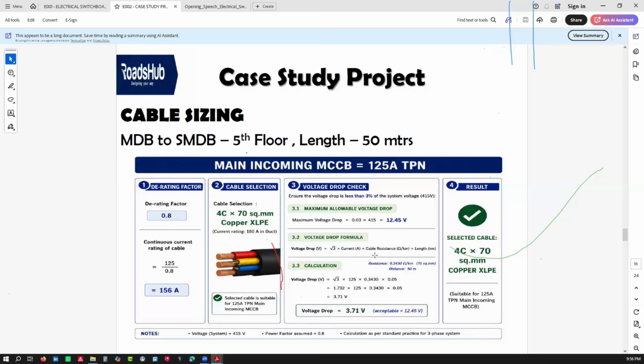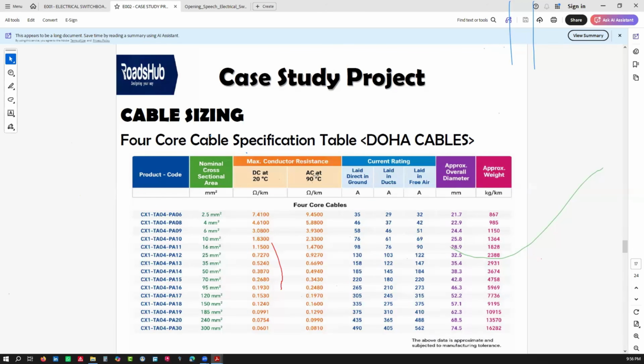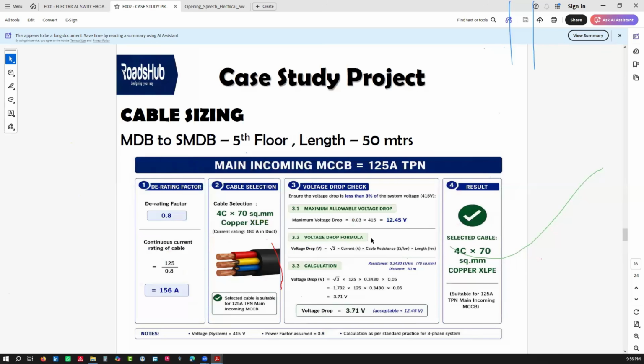So where do you get cable resistance? You have it here at 90 degrees. Always take the highest current and the highest environmental temperature that you have. So you go under 70, and then you get a 0.3430 resistance value. And then you include that value in your cable sizing. So you put your resistance per kilometer, and then your length. I'm working with 50 meters long. So let's say from my SMDB to my MDB, maybe on the 5th floor, the distance that the cable is traveling is 50 meters. You change that 50 meters to kilometers, you get 0.05. So you're just feeding into this formula to get how much voltage drops.